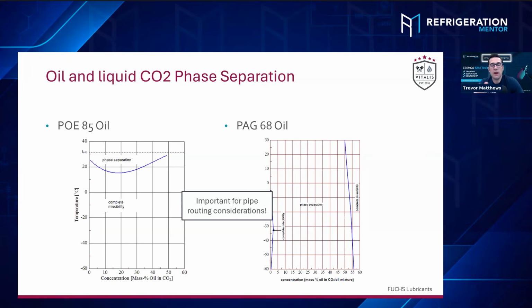Because we know all our systems that we pipe out there, we always want to slope backwards to the compressor. So, you know, all of our oils are always coming back. We don't ever want to slope out to the evaporators because those evaporators will fill. Yeah, this is piping 101. So that doesn't change for CO2 systems, that doesn't change at all, but the consideration that the liquid is not mixing with the oil is bringing totally different challenges for the liquid lines, basically, right?